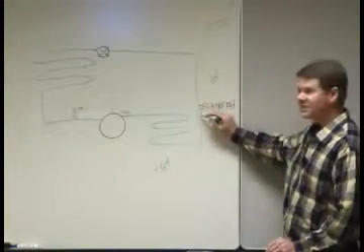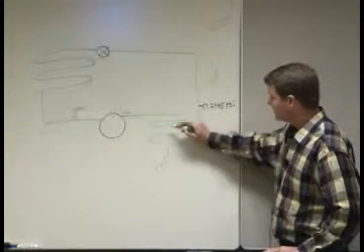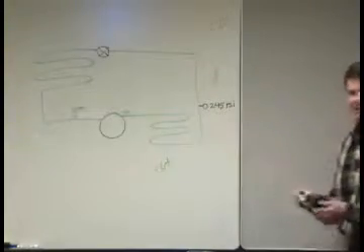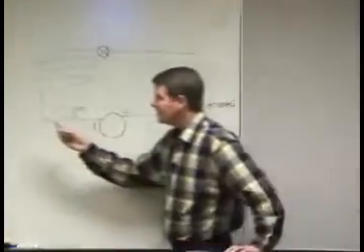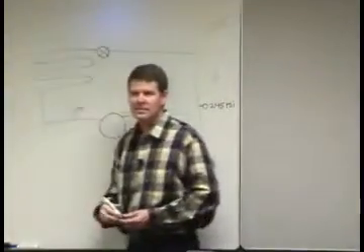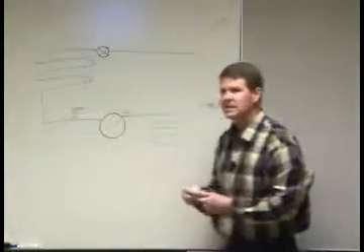So by the time we get out of our coil here, hopefully we have a steady stream of liquid 22 at 245 pounds. This air comes in at 80, 85 degrees, going out hotter, because it's got to remove all of this latent heat to get this from a vapor to a liquid. So all of that heat, that big chunk, has got to get carried away by the air. So we got rid of a bunch of heat.